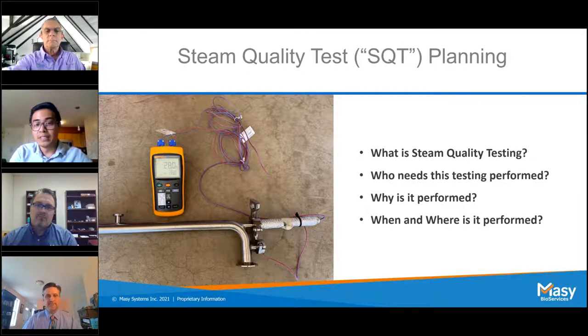In regards to when, you'll want to test your steam before any initial qualification or requalification of your autoclave, as you want to make sure that your steam meets the required EN285 requirements before moving forward with any qualification. If your steam does not meet the regulation requirements, then it may waste your autoclave qualification if the test isn't conducted before, as again, you may have issues with the quality of your steam. And I'll pass it back to you, Rob.